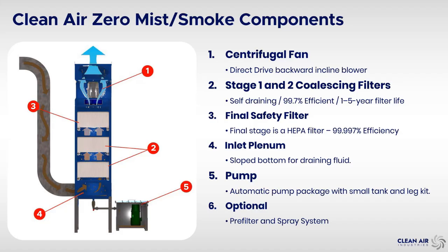So basically, the air that is coming out of our collectors is cleaner than the air that you're going to be breathing if you just walk outside. So very, very efficient. And like I said, the filters you pretty much can count on, unless it's some unusually heavy concentration of mist, you can count on them 2 to 3 years. I have seen some at 6 and 7, but however, they were pretty light applications. And then there's one other option that we also do.